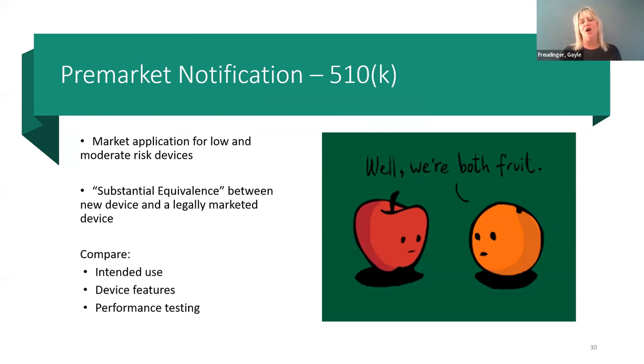Usually a 510K is often like 100 pages long, and that's not including any of the testing reports that could be necessary. The FDA doesn't publish a 510K template for you to follow when you're trying to prepare this. So you'll know the different pieces, but knowing exactly what to put in there could get a little tricky. So getting some type of support, either expert regulatory advice or someone to help you put this submission together, is really great. Then you can piecemeal the different pieces and tests as they come in, and someone can help assemble it for you and tell you what's missing, because you're going to need the summary, certification, description, equivalence pieces, the labeling, the biocompatibility, if it's software, all the details there, electromagnetic compatibility, performance testing, and so forth. So it gets really cumbersome and can be quite time consuming for you.